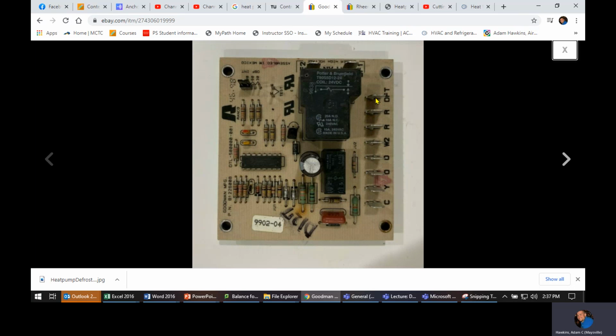DFT, this is your defrost thermostat. Oh, wait, okay, so R, this is probably R in. This is probably R to your defrost thermostat. And then this is the other side of your defrost thermostat, I'm going to bet. So between these two switches, it's going to send power to the stat, and then it's going to check that switch. And if that switch is getting power back on DFT, so if you have 24 volts right here, then it's going to sense that and tell the board, hey, we're freezing. So whenever you're ready, go ahead and bring it into defrost, whenever the timer's up.